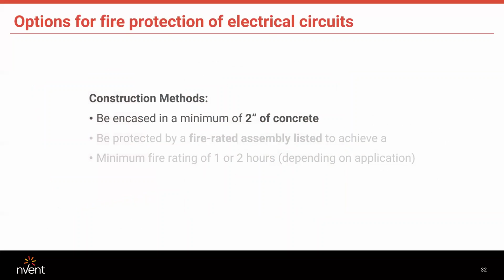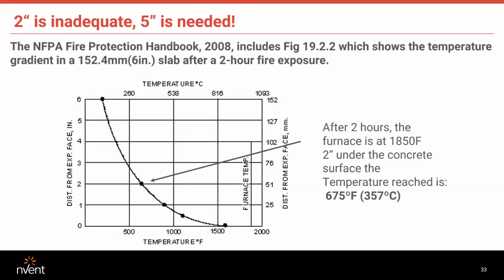And the 2 inches of concrete, actually, this is kind of an interesting slide here from NFPA's Fire Protection Handbook, which shows the temperature gradient in a 6-inch slab after 2-hour exposure. Now, why a 6-inch slab? Because they're figuring you'd have a 2-inch pipe and then 2 inches of coverage above it and below it and on each side. So it'll give you a 6-inch slab. But you can see after 2 hours, the temperature reached is 675 degrees Fahrenheit.